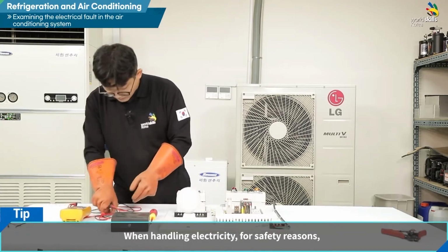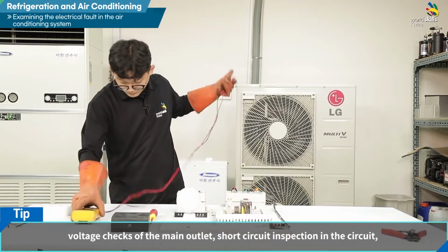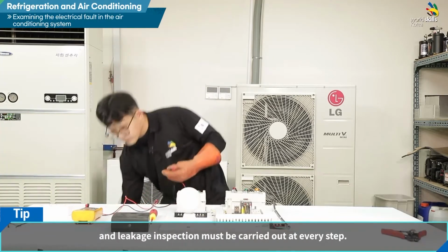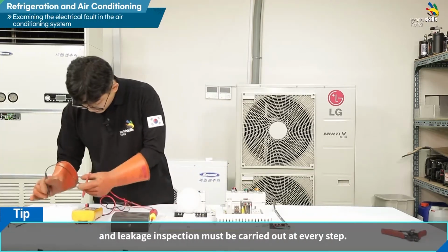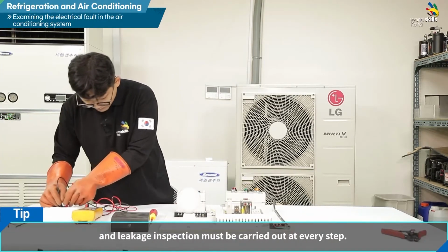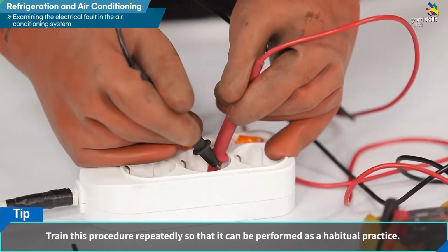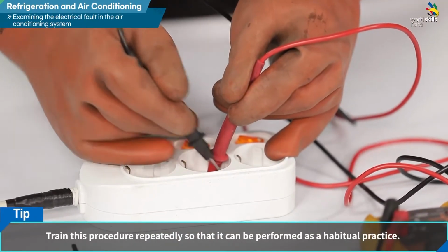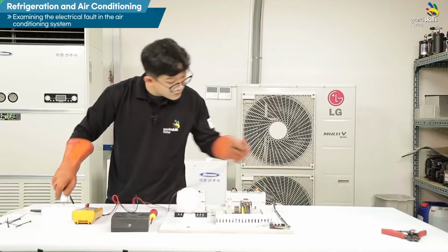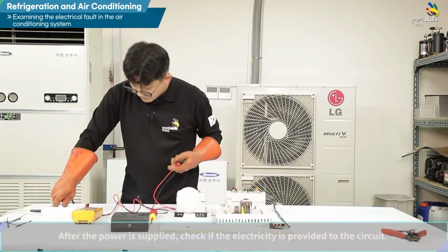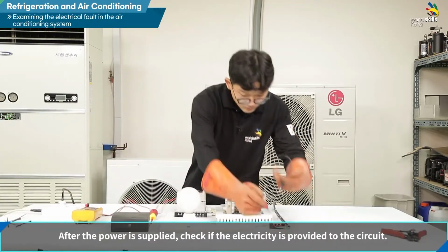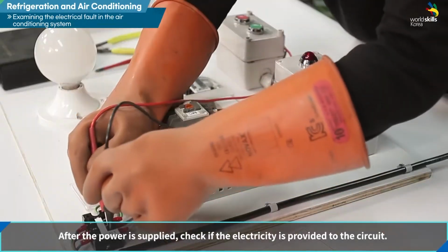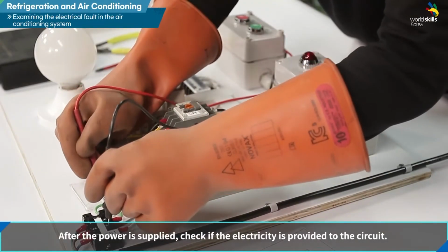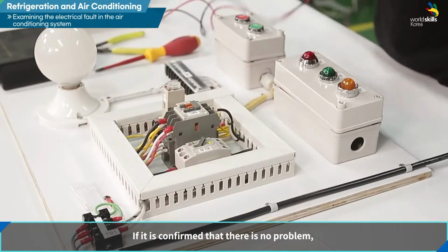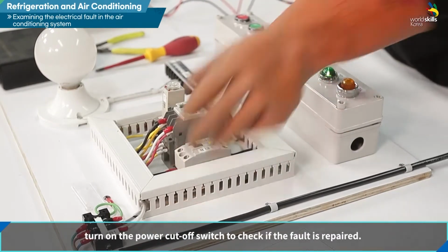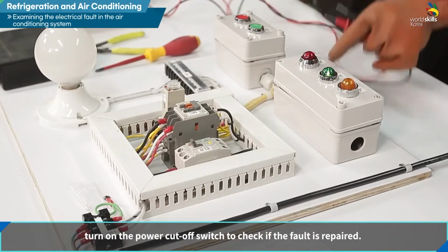When handling electricity for safety reasons, voltage checks of the main outlet, short circuit inspection in the circuit, and leakage inspection must be carried out at every step. Train this procedure repeatedly so that it can be performed as a habitual practice. After the power is supplied, check if the electricity is provided to the circuit. If it is confirmed that there is no problem, turn on the power cutoff switch to check if the fault is repaired.